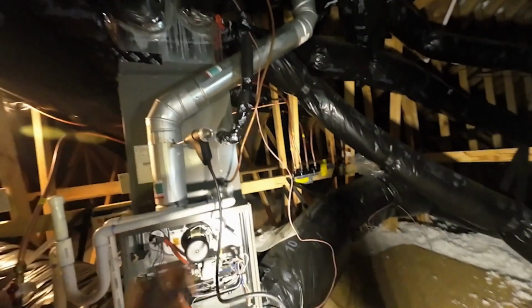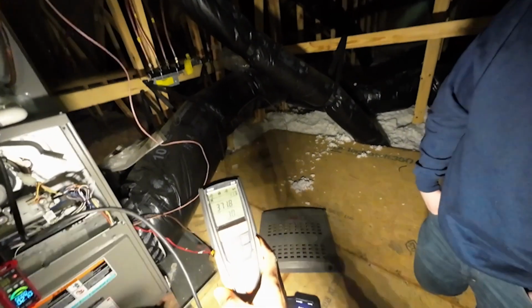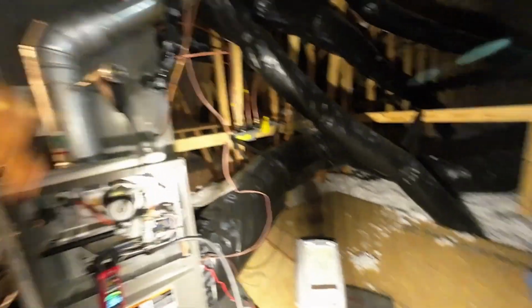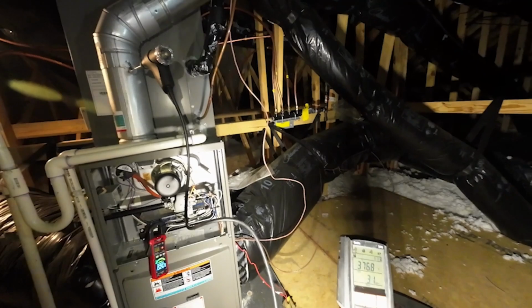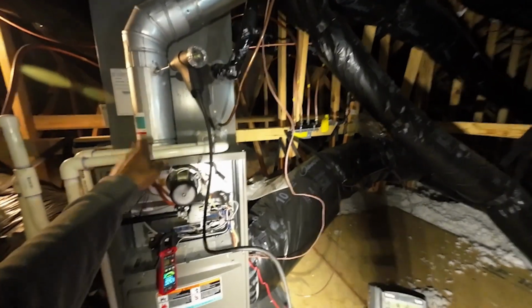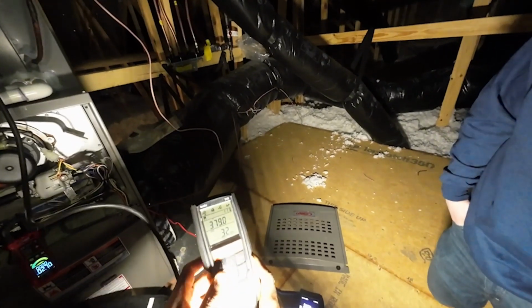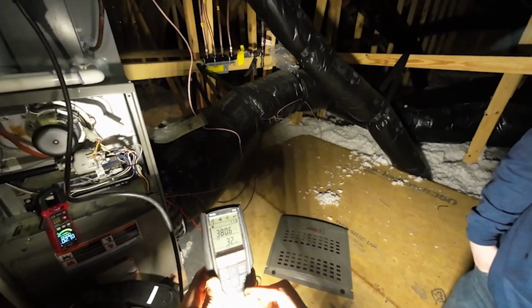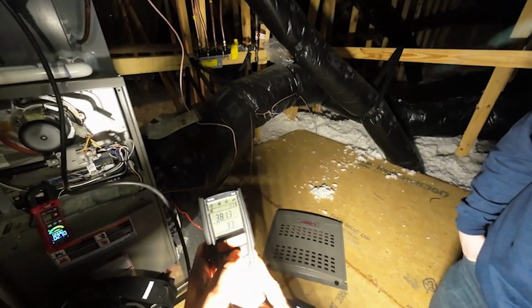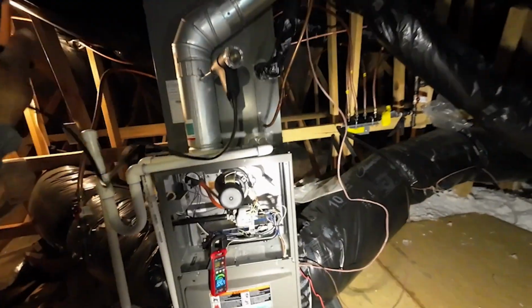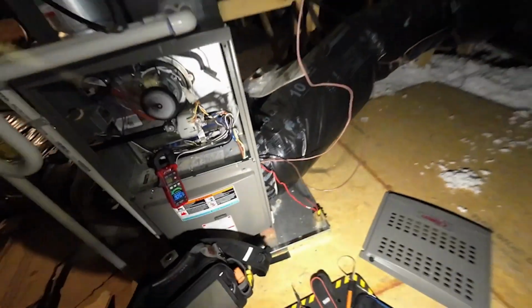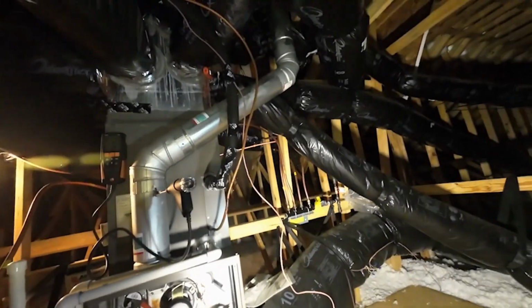Stack temperature, that's the temperature of the gases exiting. So that's pretty much what that's going to tell you, how efficient the system is running. That's going to help calculate efficiency. The hotter those gases are, guess what that means? The more heat is getting out of the house, the less efficient the system is, right? The more heat I can pull out of these gases before they're exiting, the more efficient the furnace is going to be. You want that to be between probably 380 to 450 degrees, something to that effect. Suffice to say, this is a way of testing the furnace combustion and how completely it's burning the fuel.